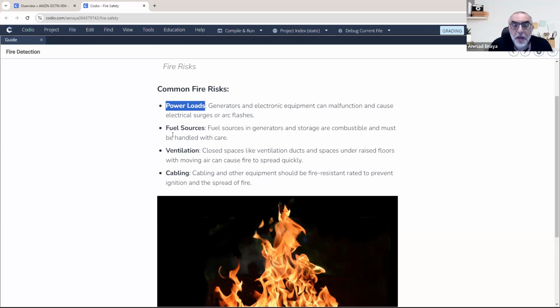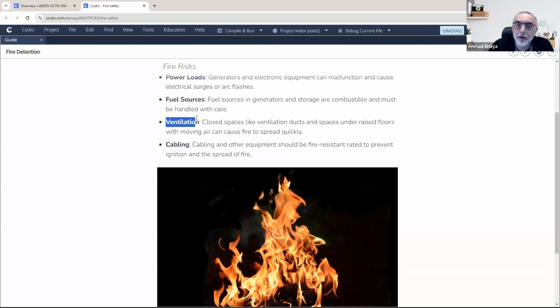The other thing is we have generators in data centers, and generators need fuel. If you don't store it properly, it's combustible and may cause fire to spread. Sometimes ventilation works against us too. With ventilation, fire can spread easily within a data center, because with the flow of oxygen, the fire can flow from one room to another. So this is something that can work against us in data centers.